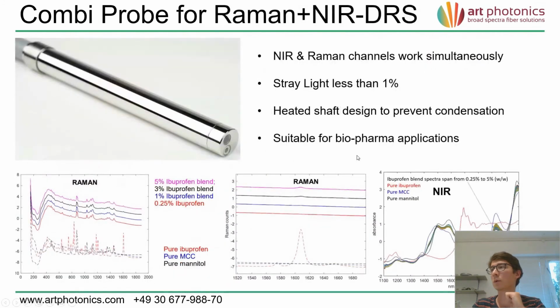Here I also wanted to present our unique probe for Raman and near-infrared diffuse reflection. These two channels can work simultaneously. The stray light in the diffuse reflection spectroscopy channel is less than 1%. It's very important for such applications. For example, in pharma applications, the shaft is specially heated so that there are no condensations on the windows. This probe is made for industrial applications.